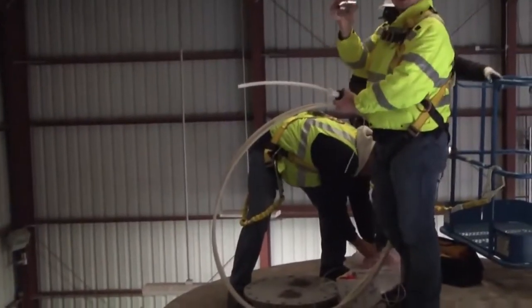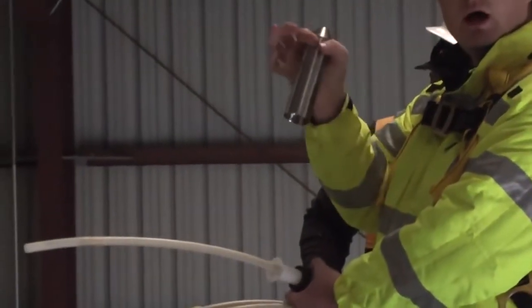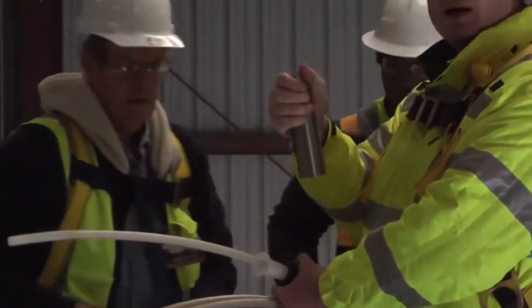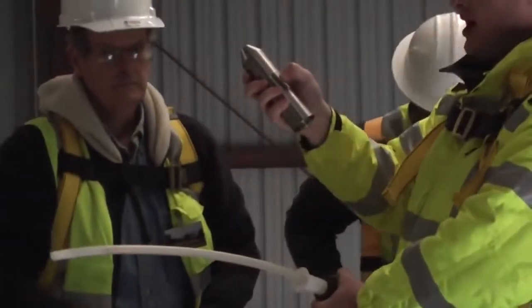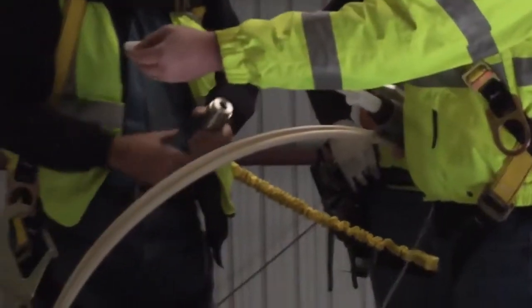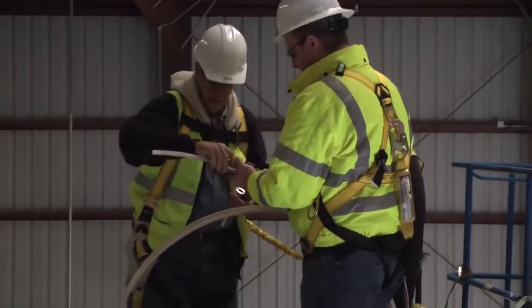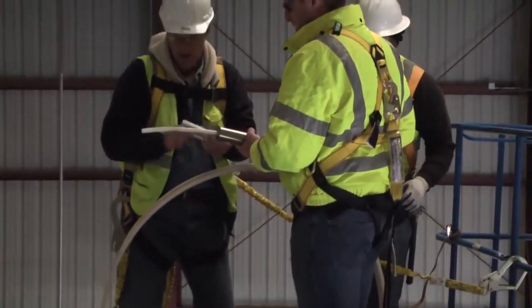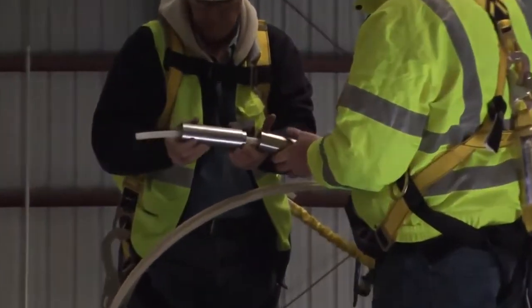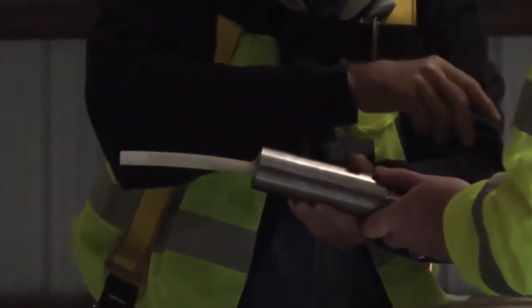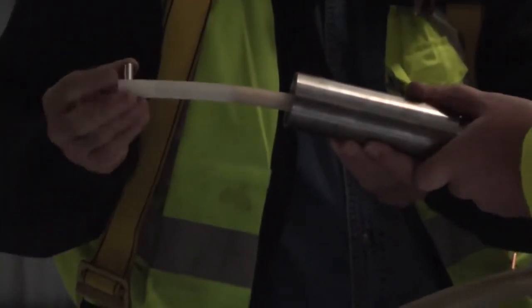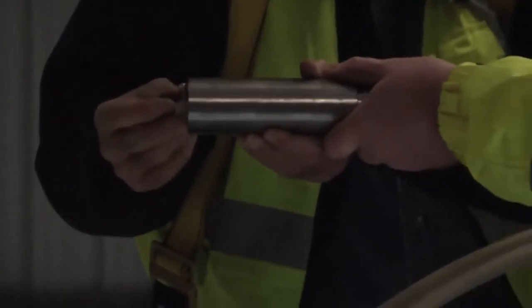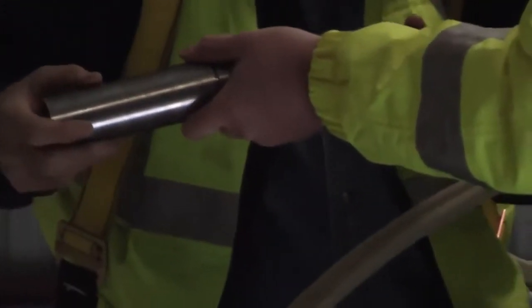Now, depending on the length of your probe, you may have 1 weight or 2 weights. The weight is always going to be the same design. It's going to have the teardrop design. And also when you have the water float, it will come down on the top of this weight right here. You have your pin. It's going to go on the end of the probe, and this is what's going to keep your weight on. It's going to keep the float and everything else on too. You want to make sure you get all the tape off, because if you leave some of the tape on, it might disintegrate into your product. So you have your little pin, make sure you don't drop this. Now it's really important that when you get these weights on, you start supporting the probe.